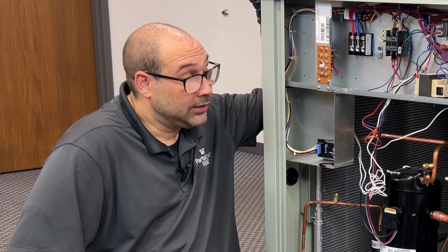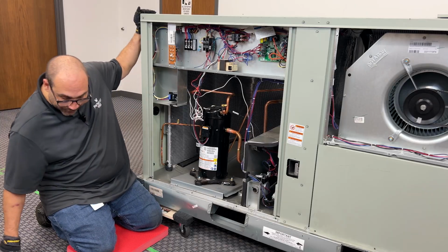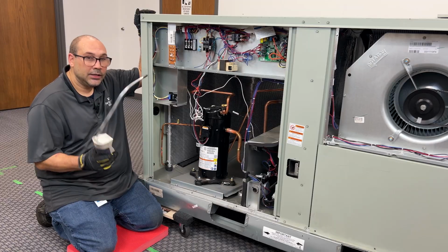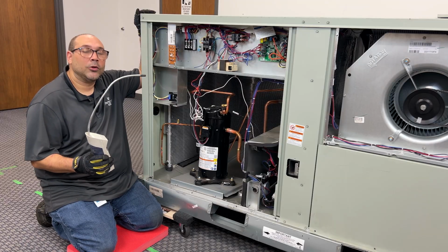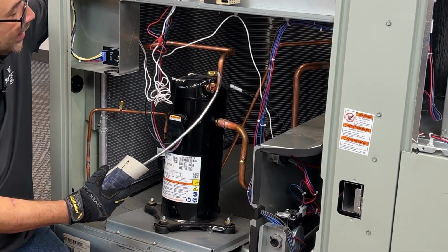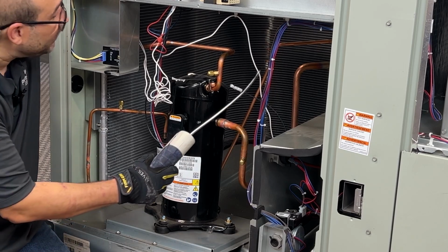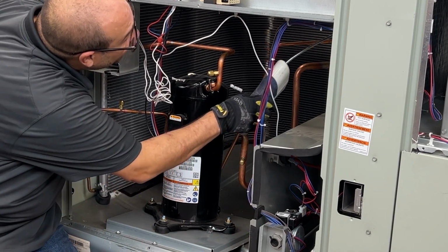Okay, so you've gone through the evaporator coil, you've gone through the condenser coil, and still can't find that leak. Now you're going to start looking at your fittings and your braze joints. First thing I'm going to do, I like soap bubbles, but when I'm trying to get a general area of a leak, I'm going to use my electronic leak detector, and I'm going to go at every place that I see braze, and I'm going to listen for the tick. Beep, beep, beep. Right, there's the TXV back here.